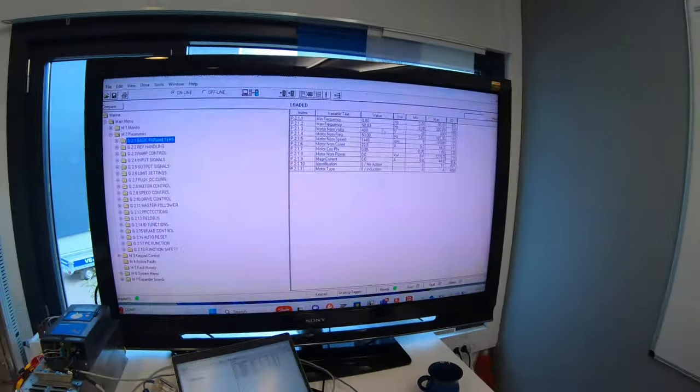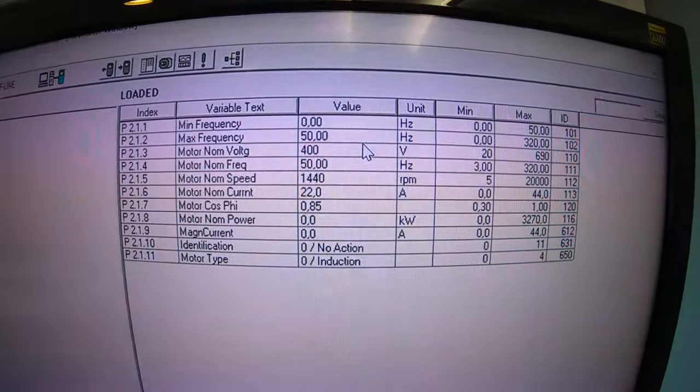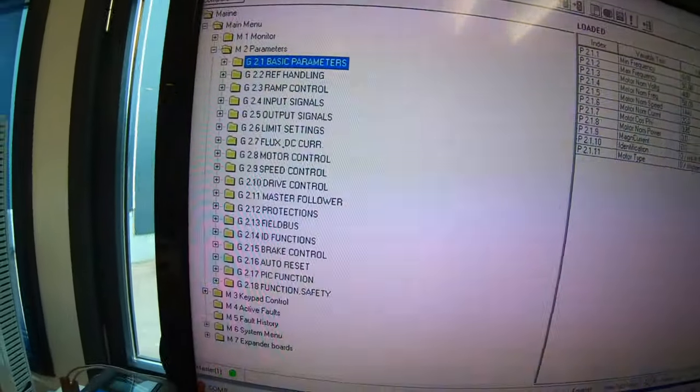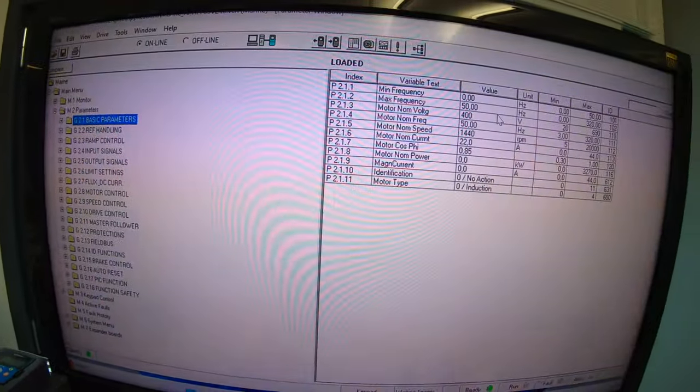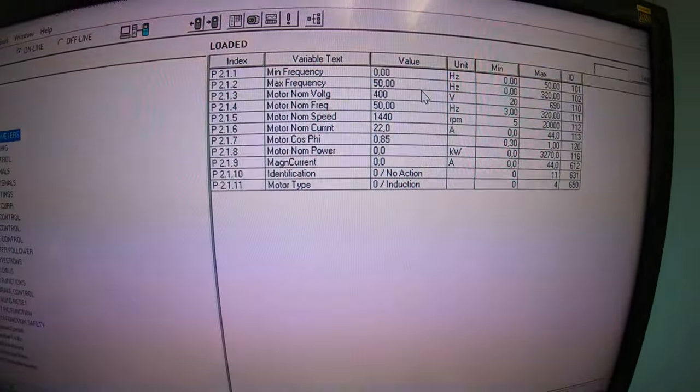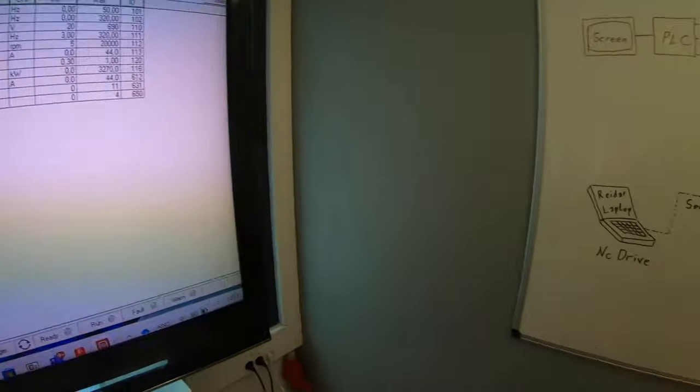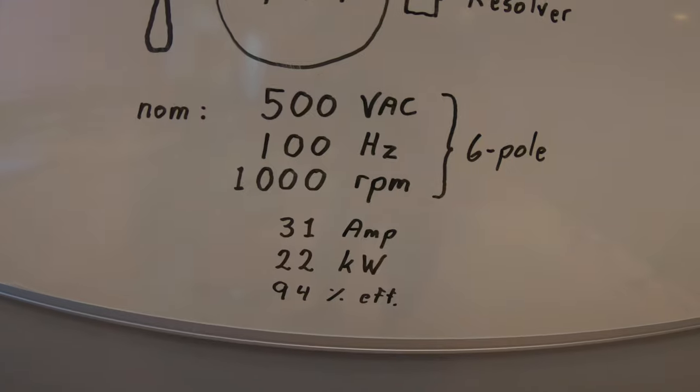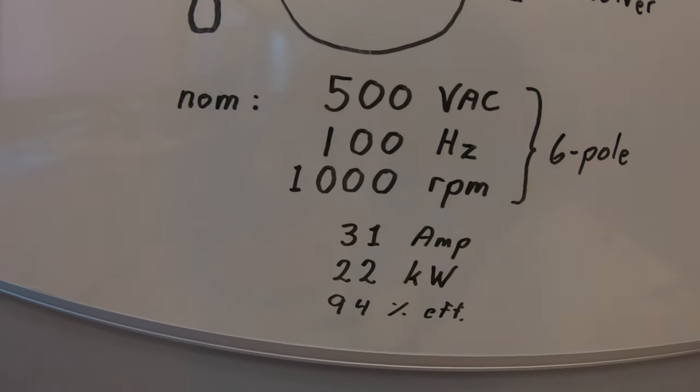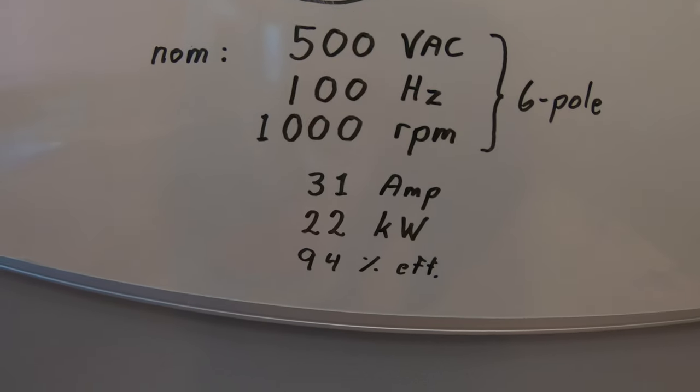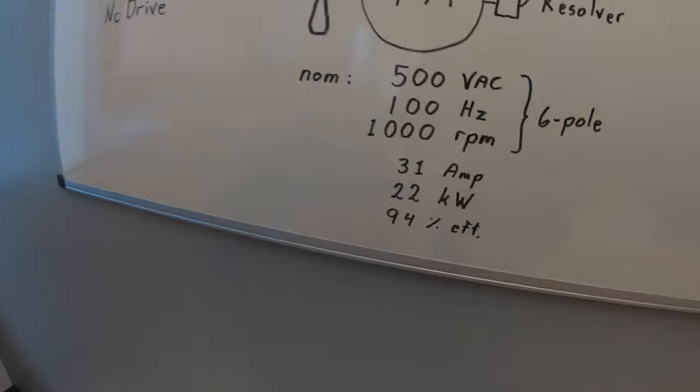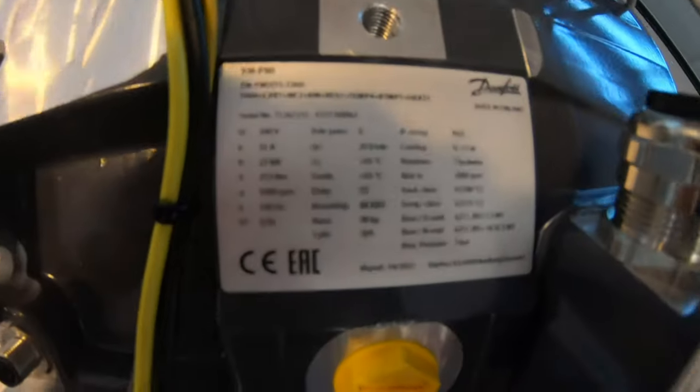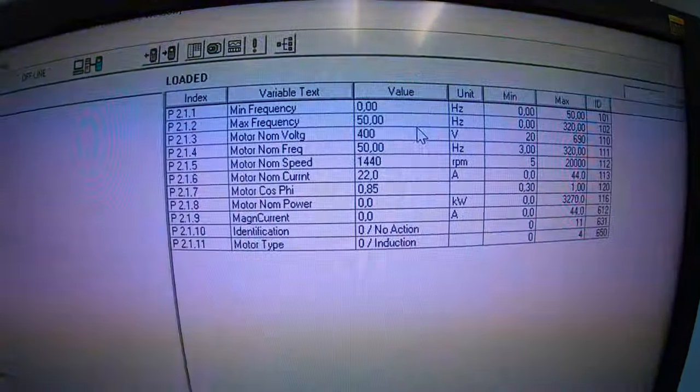The minimum amount of parameters that we have set is the motor nominals and selecting what type of motor and some few other stuff in the motor control. The motor nominals are voltage, frequency, RPM and especially this is really important for the drive to know the pole number. Amperes and kilowatt and efficiency. Everything is found here on the motor plate.